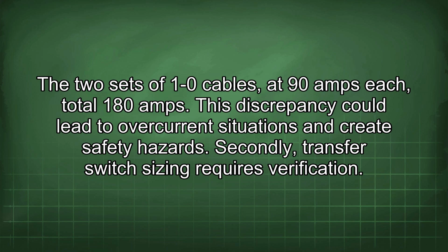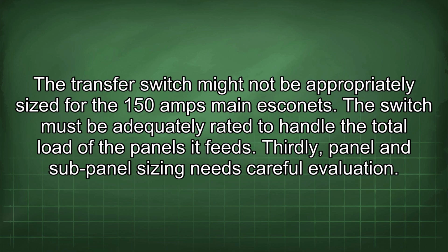Secondly, transfer switch sizing requires verification. The transfer switch might not be appropriately sized for the 150 amps main disconnects. The switch must be adequately rated to handle the total load of the panels it feeds.